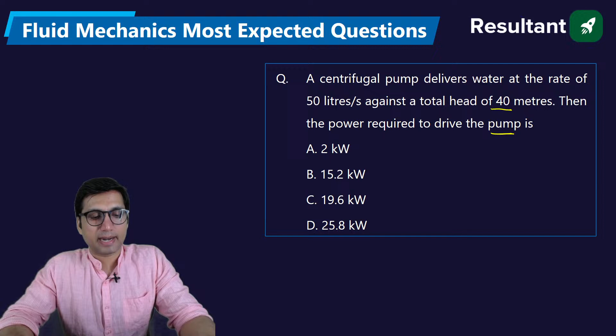So how do you find the power required to drive the pump? You know that it is a centrifugal pump, and obviously it will be delivering water, right? So the power required to drive the pump is equal to rho g q into h. Now this is a formula, but you have to find it in kilowatt. So to find it in kilowatt, you have to divide by 1000. If you don't divide by 1000, you will get the answer in watt.